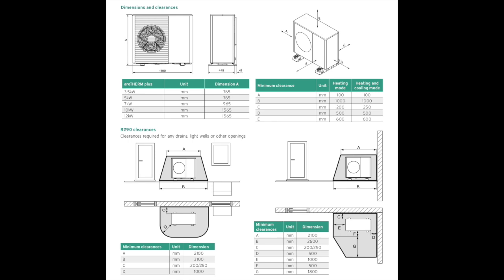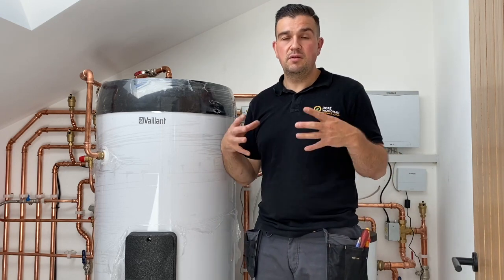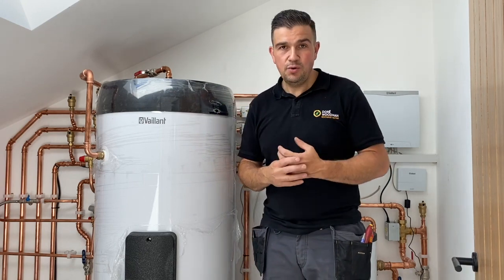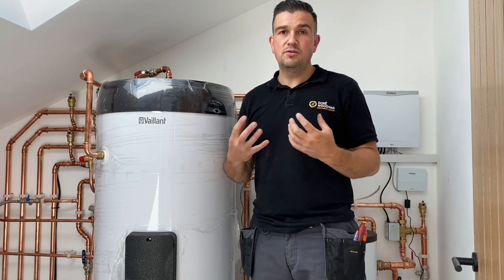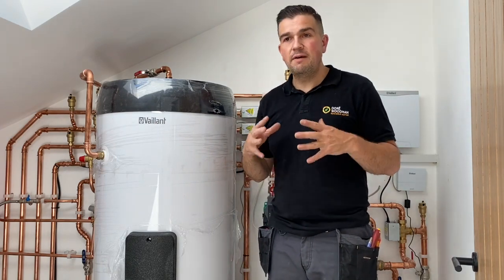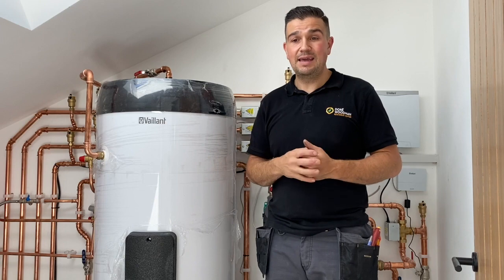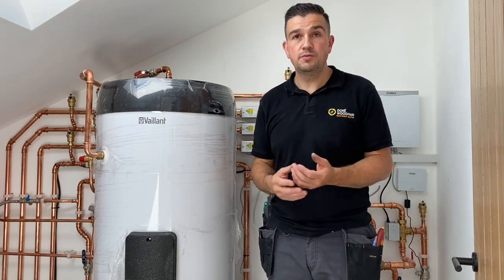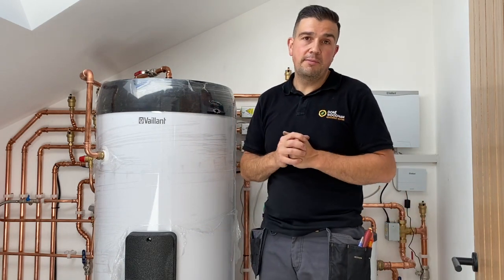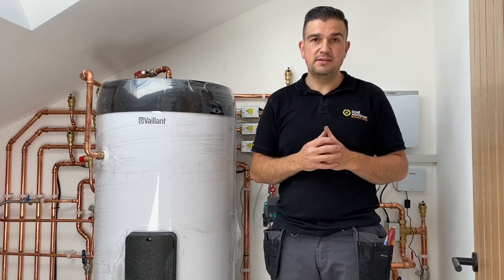The refrigerant used in the Vaillant aroTHERM plus is R290, which is propane — a flammable, explosive liquid. It's a double-cased system with many safety vessels and devices attached to minimise any risk, such as a refrigerant leak. Being propane, it's heavier than air and drops to the ground, so the unit has to be away from doors and windows to prevent it seeping indoors. There are clear parameters we work within to make it very safe for the homeowner, and these are a required part of any installation.